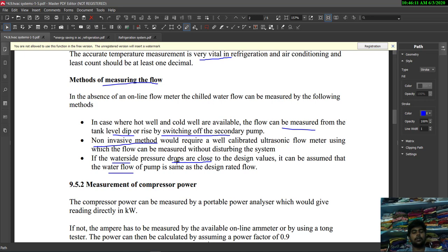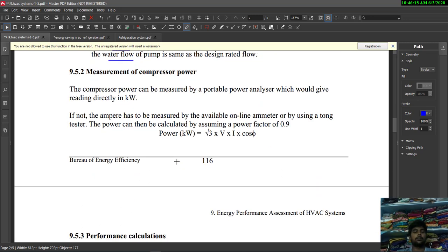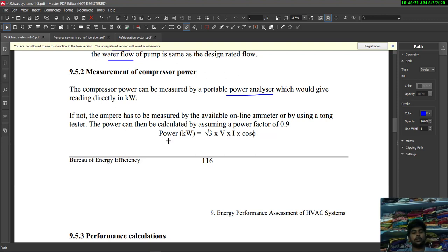If the water-side pressure drops are close to the design values, it can be assumed that the water flow of the pump is the same as the design rated flow. Next is measurement of compressor power, which can be measured using a portable power analyzer giving a direct reading in kilowatt, calculated as: Power = √3 × voltage × current × power factor, where power factor is assumed as 0.9.